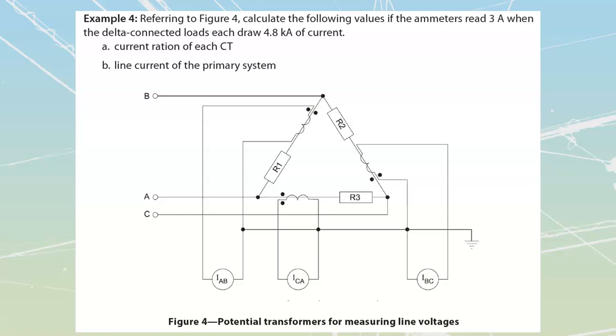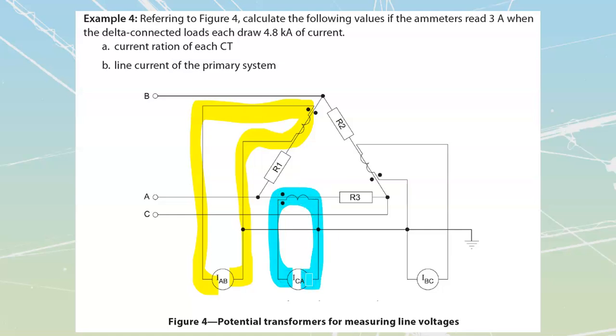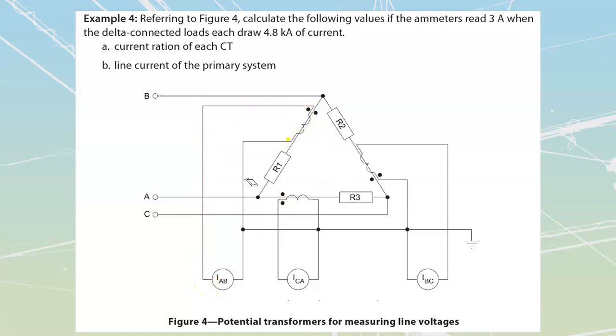Okay, next one over here. We're going to use CTs to measure phase currents. And if we measure our phase currents, then we can figure out our line currents as well. Once again, do I care about the fact that I have this line connected across here inside of a delta? Absolutely. Or inside of a Y? Absolutely not. Because we're going to see that the current generated by this CT is only going to go to this meter, and the same with the other subsequent meters. The reason for that Y point is safety, as we have already said so many times before. All right, let's calculate the following values.